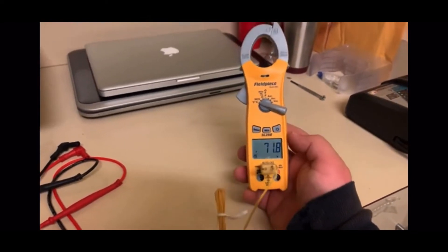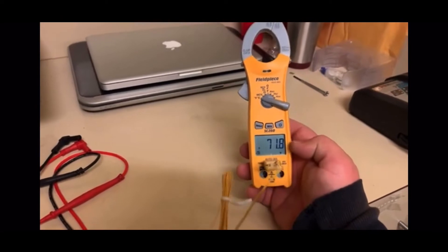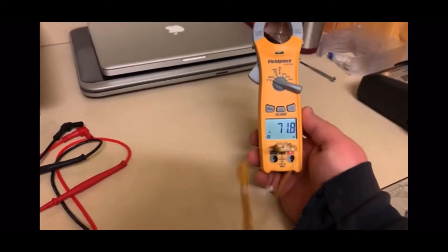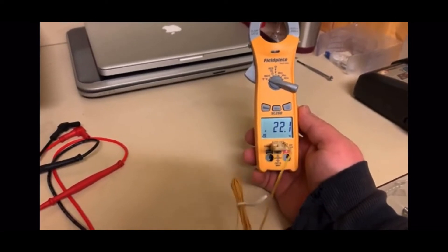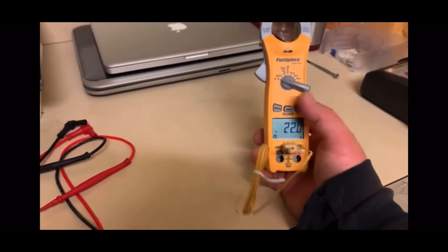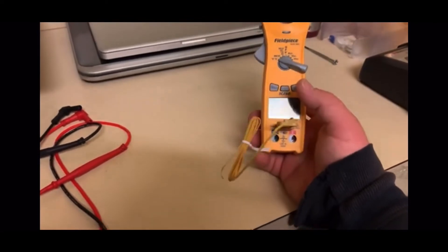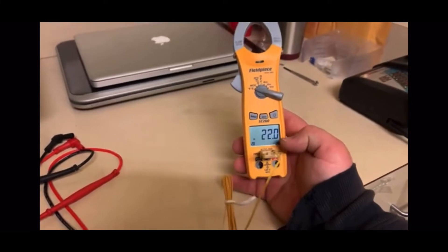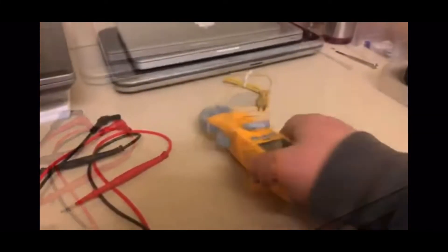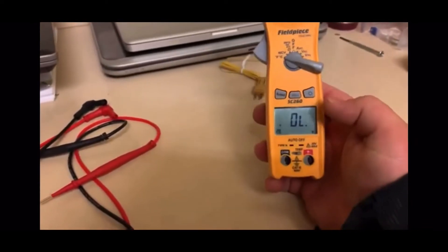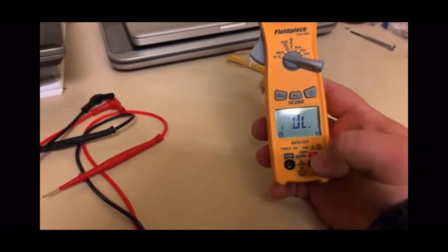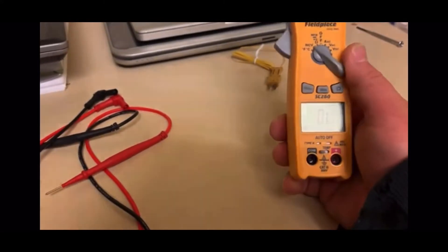For those who use Celsius, you just press select and it will change to Celsius. Now it's 22 Celsius, the equivalent of 72 degrees. You put this end of the wire on the pipe and check the temperature to take your subcooling or superheat, depending on what system you're working on.